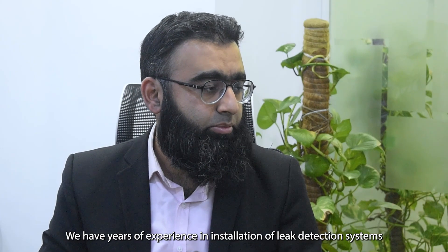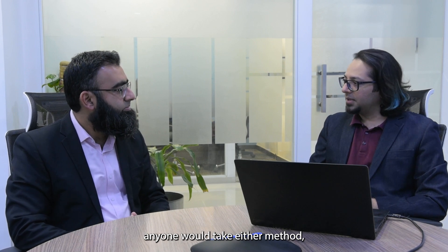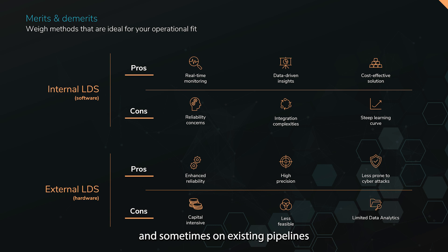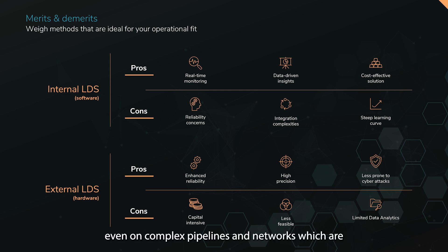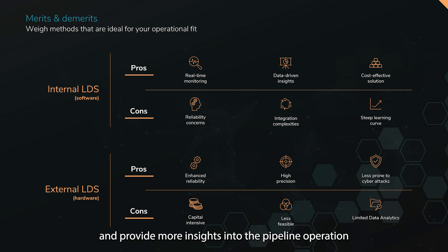We have years of experience installing leak detection systems on complex and long-distance pipelines. External systems based on fiber optic are generally considered a more reliable form of leak detection, but these benefits come at significant capital cost. On existing pipelines, it is often not feasible to install fiber optic-based systems, especially on complex pipeline networks already in operation where it is hard to invest heavily in external hardware LDS systems. Software-based systems are less expensive and provide more insights into pipeline operations and leak scenarios that are otherwise not possible with external systems.